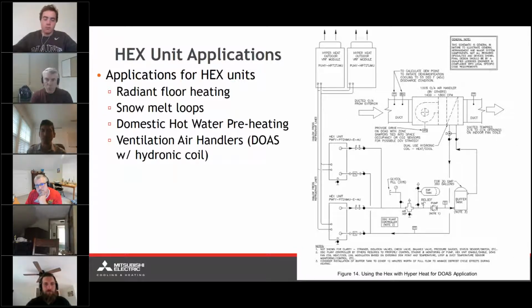And lastly, here's an example for tying the HEX unit with a DOAS system or an air handler unit with a hydronic coil. Since the HEX units are connectable with City Multi equipment, we could get extended heat pump range with your VRF indoor units, as well as providing a DOAS unit coupled to potentially a hyperheat product or a low ambient heating product. So you've now tackled both your comfort heating and cooling and your ventilation demands, and designed around the pretty extreme colds that we see in the Northeast environment.